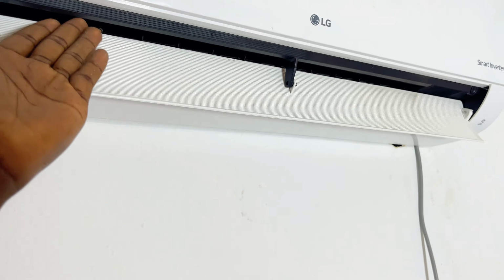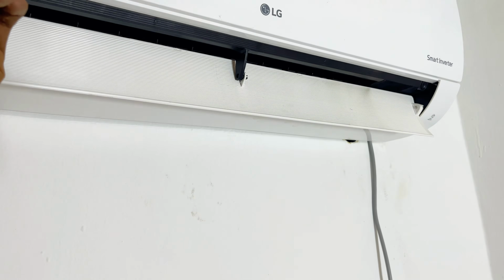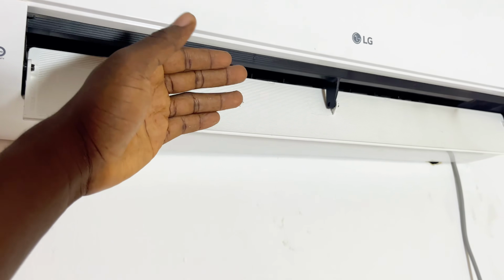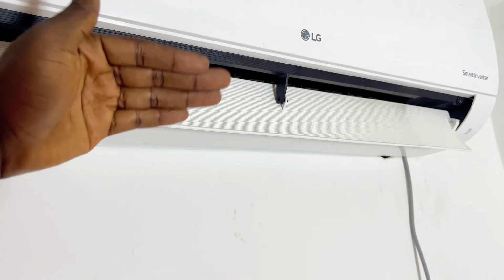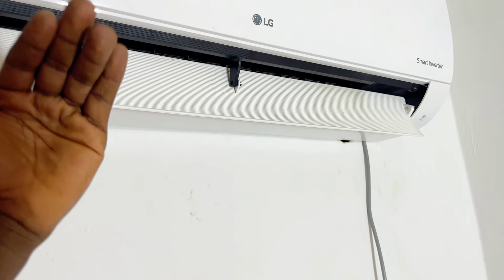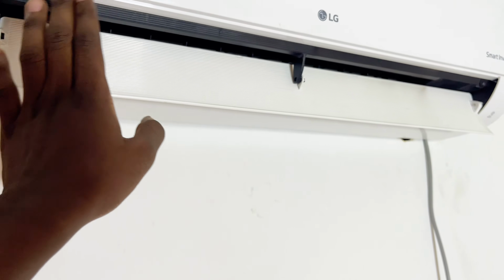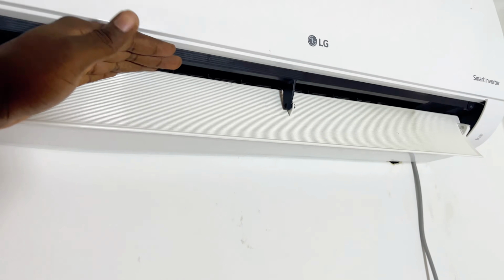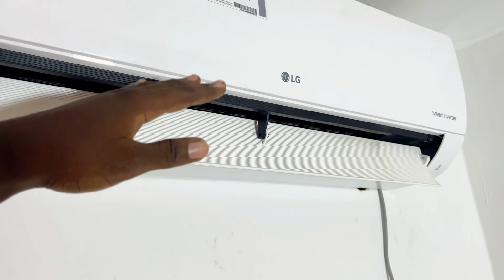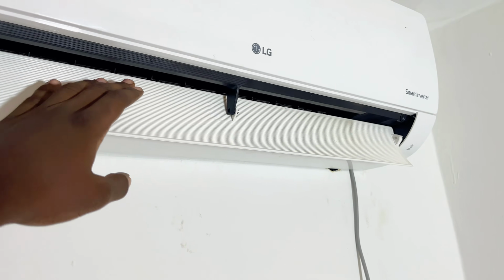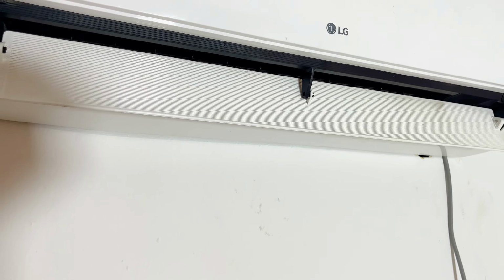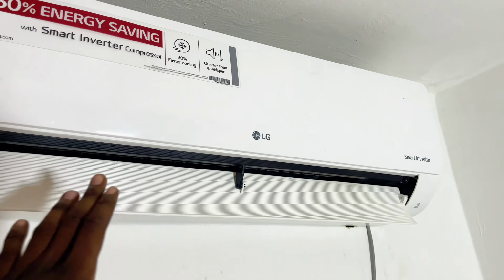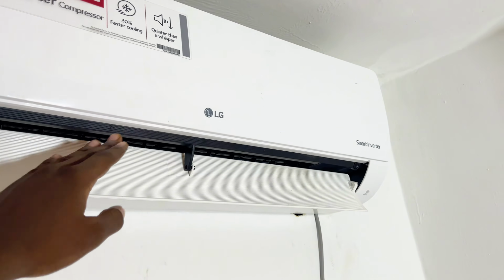One is the fact that there is too much of dust inside of the fan motor, and it is basically stopping the AC fan motor from rolling and bringing out air from inside of the AC to inside of your room. Another thing that might actually be causing the issue is if the cable that actually connects the fan motor to maybe the panel of the AC or just the power source that actually powers the fan motor is not working. In that particular case, you're going to get the CH10 error. And for that, what will actually solve your problem is to simply just go ahead and change the cable.